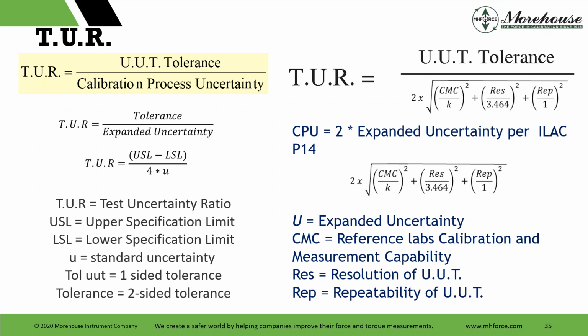So then we go back into TUR, which is virtually maintainable, as the uncertainty is cumulative, right? So you may start on a TUR situation with 0.1 pound, and then the next lab may be 0.15, and then 0.2, and then 0.3. And you just keep processing that uncertainty. And the TUR for that definition is UUT tolerance under calibration.